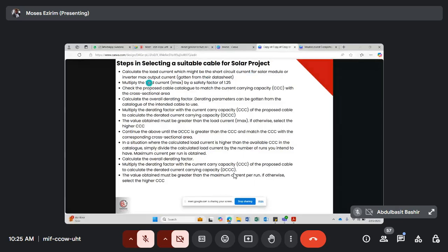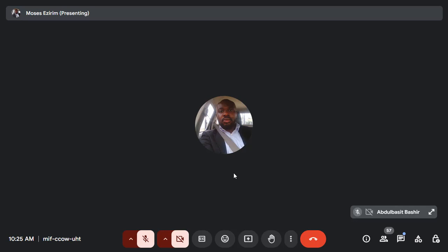Now, if you're going to size your cable for a solar system, ensure the first thing is to know your current and the derating factor I will use. And once you've done that, you now check the proposed cable catalog to match the cross-sectional area. All right, so now let's start.